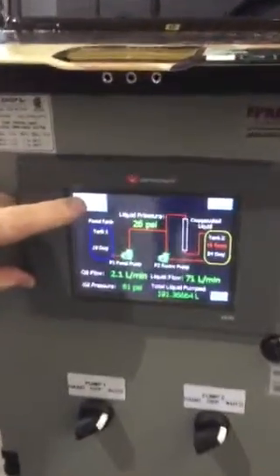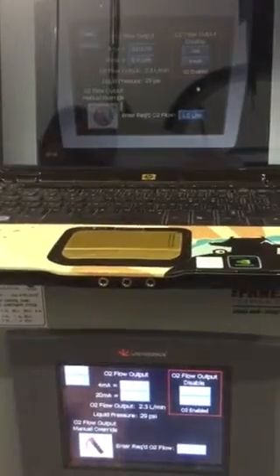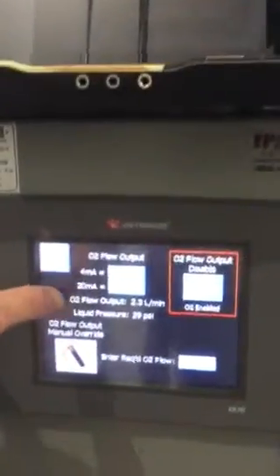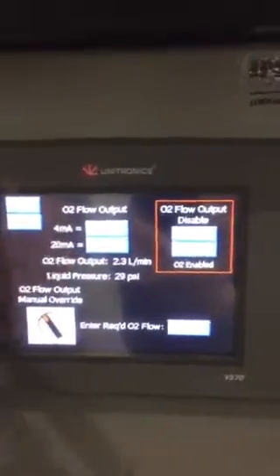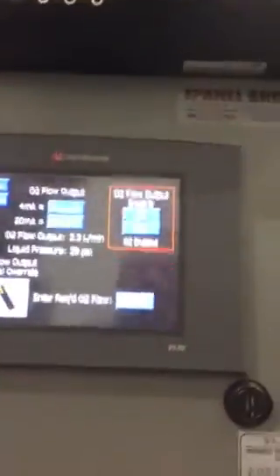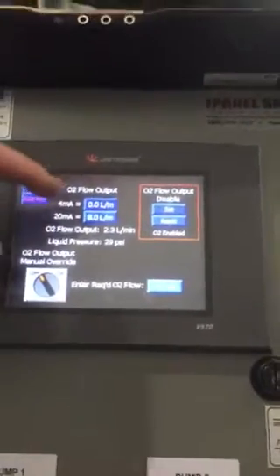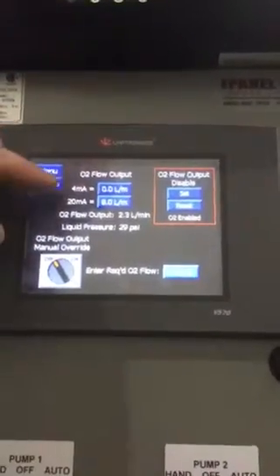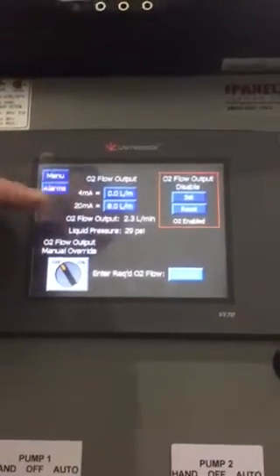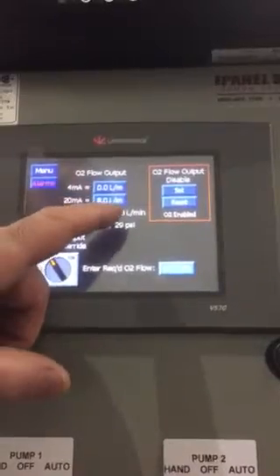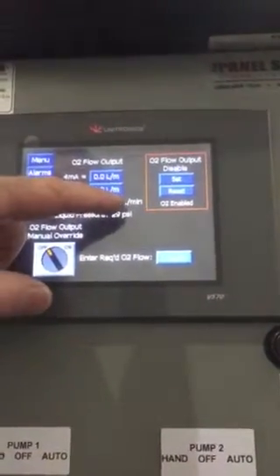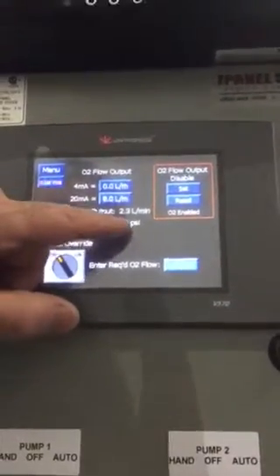It's very versatile. Now to go back to the menu button on the left side, we hit the menu, and then we go down here to oxygen flow output. What we have on this screen is a flow output that's 4 to 20 milliamp equals 0 to 8 liters per minute. This is just the calibration that I use. Don't touch that. So we have 4 to 20 milliamp, which is equal to 0 to 8 liters per minute. So I've just done a calibration to make sure that at the flow rate that it's at right now, this is the actual reading. It's 2.3 liters per minute with liquid pressure of 29 psi.